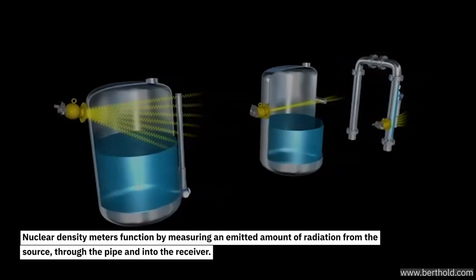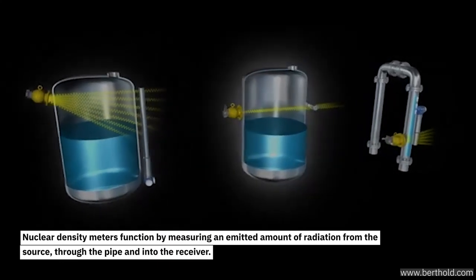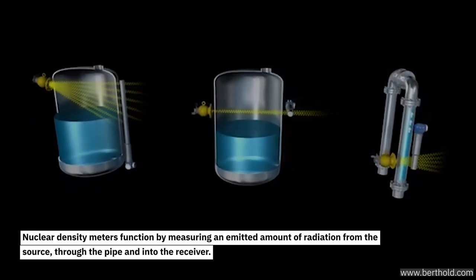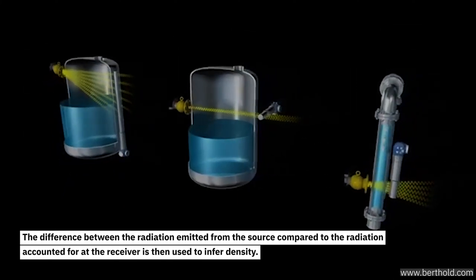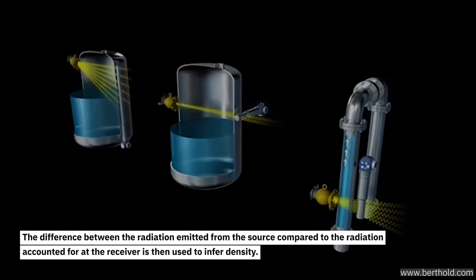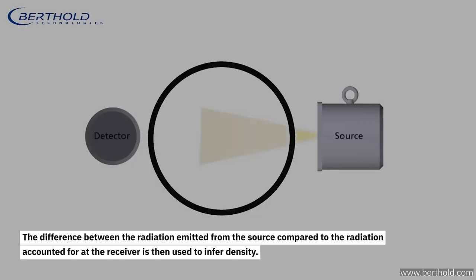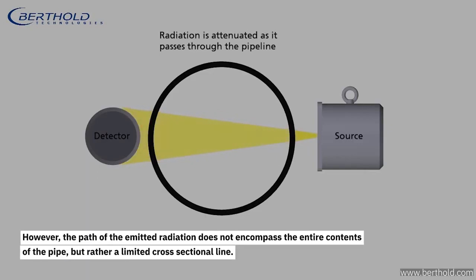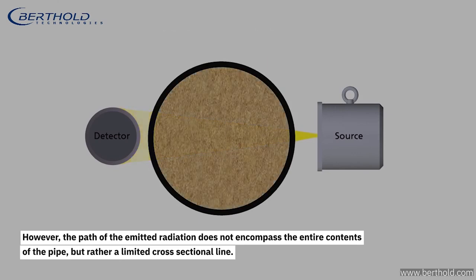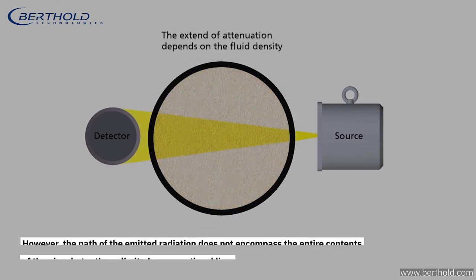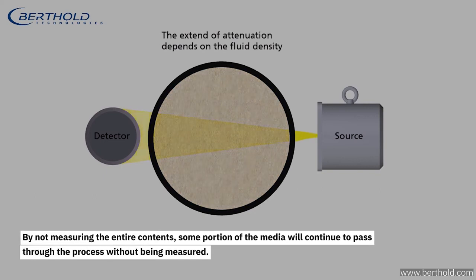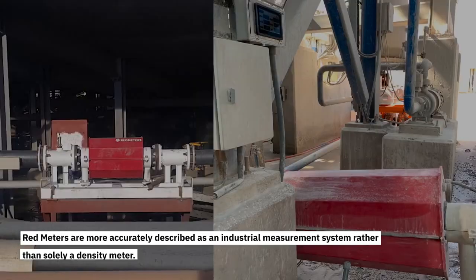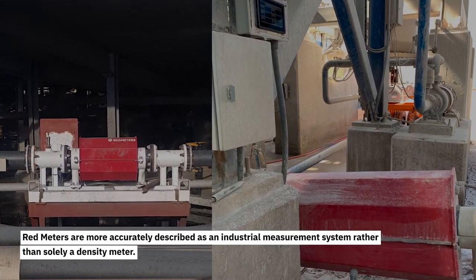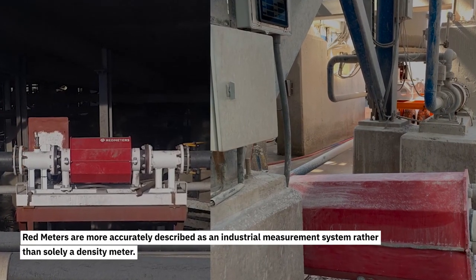Nuclear density meters function by measuring an emitted amount of radiation from the source through the pipe and into the receiver. The difference between the radiation emitted from the source compared to the radiation accounted for at the receiver is then used to infer density. However, the path of the emitted radiation does not encompass the entire contents of the pipe, but rather a limited cross-sectional line. By not measuring the entire contents, some portion of the media will continue to pass through the process without being measured.